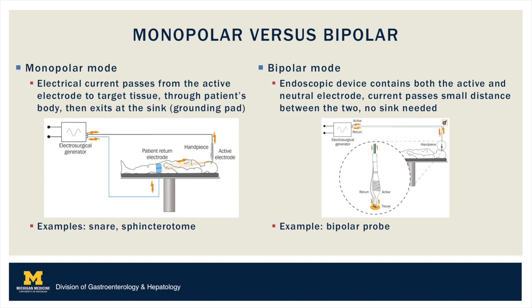Electrosurgical generators have both monopolar and bipolar modes. In monopolar mode, the electrical current uses the body as the medium through which the current passes, ultimately exiting from the grounding pad. Examples include hot snare or sphincterotomy. In bipolar mode, the endoscopic device contains both the active and neutral electrode, and therefore the grounding pad as a sink is not needed. An example of this is the bipolar probe.